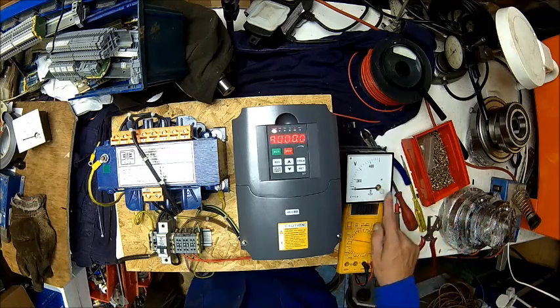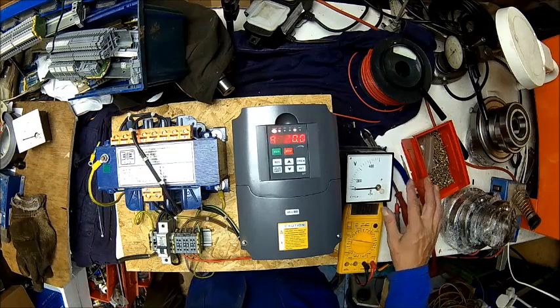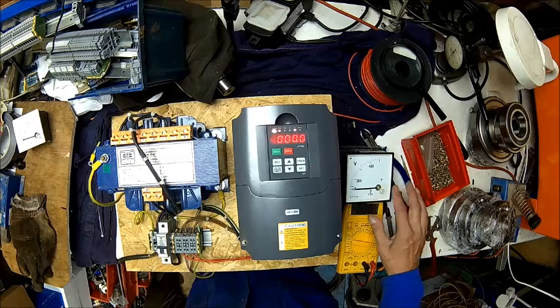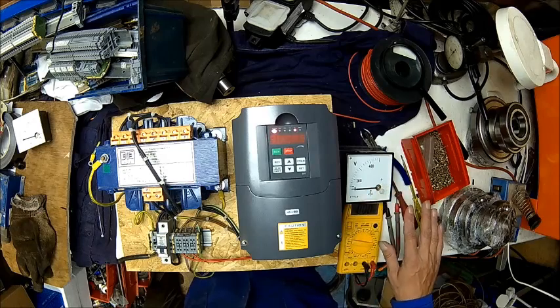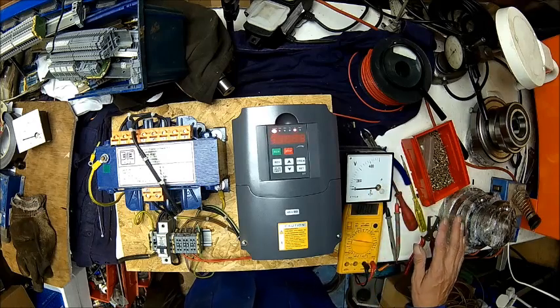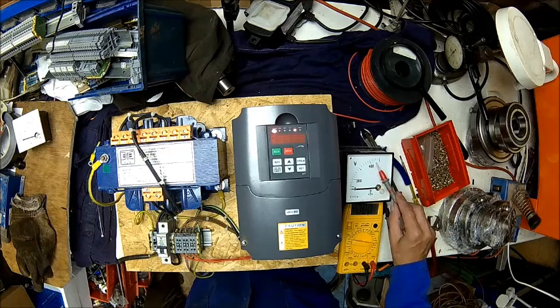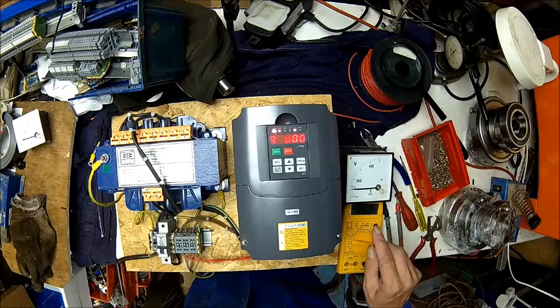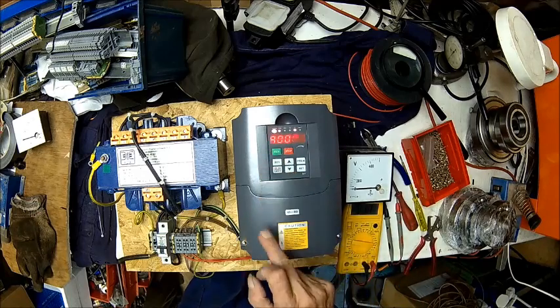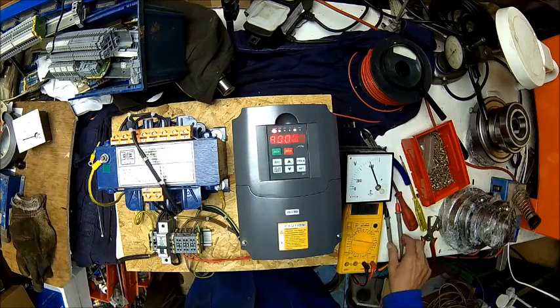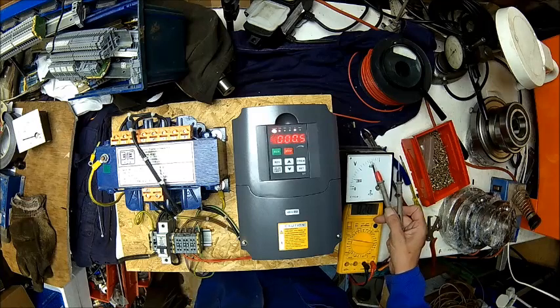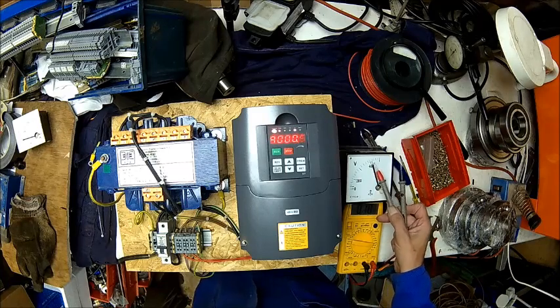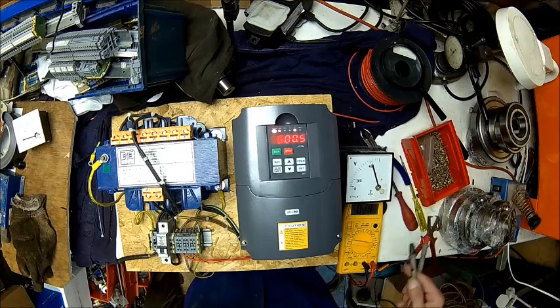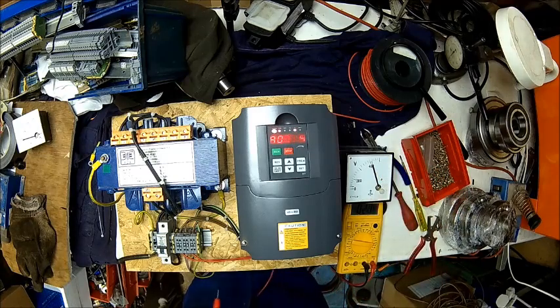So we hooked up a good old analog meter, which is a moving magnet one, a pretty slow responding panel meter. One division is 20 volts, so that's 400, that would be 420. We fire it up, and you see the voltage is coming up, and we're reading between 410 and 415, which is okay because it's a good old meter.